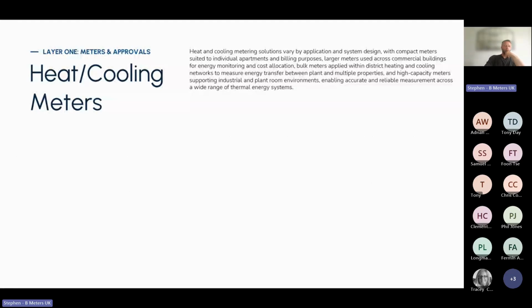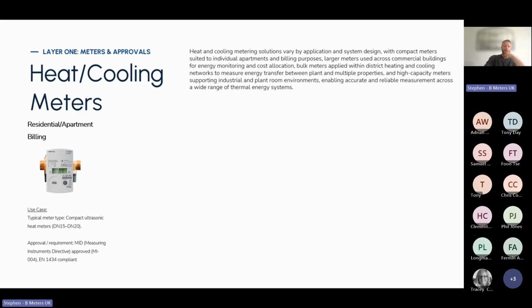Now, heat and cooling meters tend to be a little bit different, because the variation comes on what type of site and what type of requirement. So, for example, residential apartment billing, the typical meter would be a compact ultrasonic heat meter, DN15 to DN20, like the Landis+Gyr T330. Very cheap, very cost effective, meets the requirements, and has a good, robust lifespan. So, even battery powered, you'll get 11 years out of these meters. And if the batteries need replacing, on the newer versions they can. The approval requirement is always going to be MID 004 EN 1434 compliance.